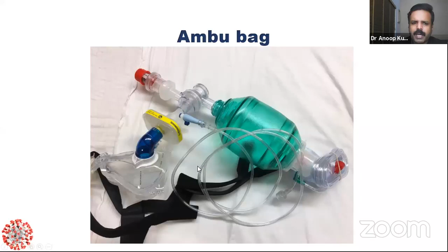We have to always use a non-vented mask. If possible, you get a full face mask, followed by a filter. Then you should have a leak port here, and again, this leak port you should not cover. Oxygen you can connect at this point, or if that is not possible on some other machines, you can connect the oxygen to the machine, to the port where you can usually connect the oxygen. So this is how you usually connect the circuit.